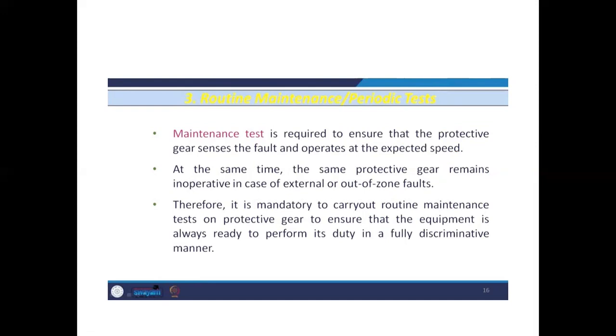If proper maintenance is not carried out, the life of the protective relays will go down. So in order to increase its stability and its operating life, we have to periodically perform these routine tests. Maintenance tests are required to ensure that the protective gear senses the fault and operates at the expected speed. For all protective devices, there is a specific operating time. If it is not working within the provided operating time, it is slow in operation. When a fault occurs, it trips slower than the time provided on the rating of the circuit breaker or the relay.